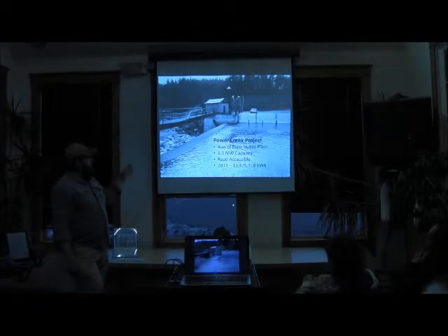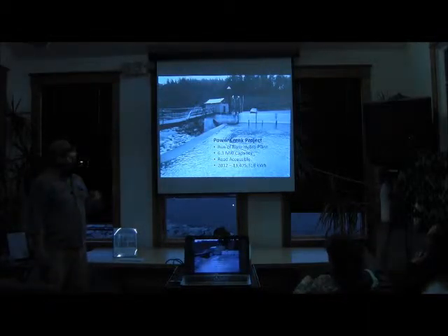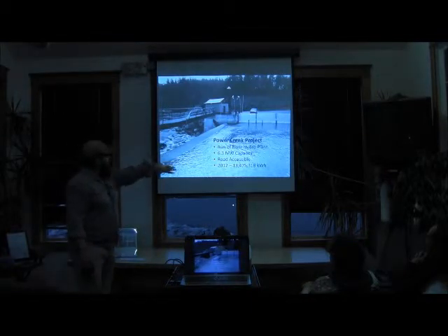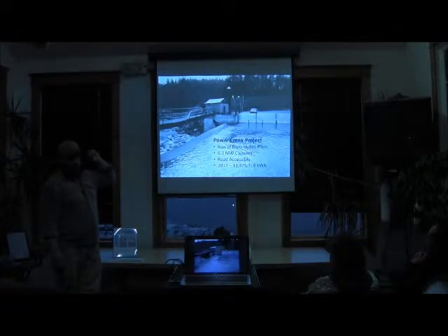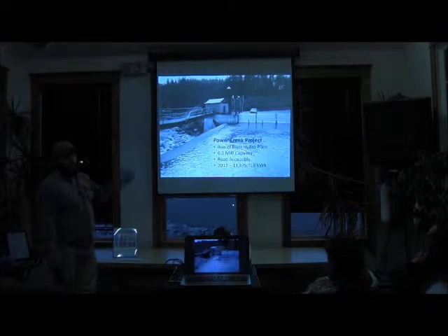So Power Creek is our largest run-of-river plant. It's a 6.3 megawatt capacity. There are 2 generators there, 2 big turbines. It's road accessible. In 2012, a little under 13.5 million kilowatt hours were from that plant. And you can see it here. There's a little reservoir. It's not very big. There's no storage. It's all run-of-river. So when it stops raining or snow stops melting, we run out of power up there. And this rubber dam, we can raise and lower if we need to spill water for different situations.